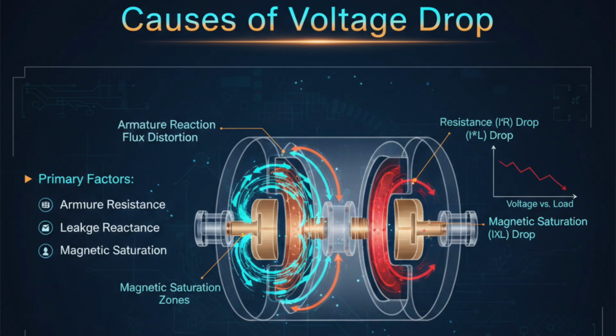Another major factor is armature reaction, the magnetic field created by stator currents that distorts or weakens the main rotor field. You can see this effect represented by bent and distorted flux lines in the graphic. Magnetic saturation of the core also limits how much additional flux can be produced even when excitation is increased. Together, these phenomena explain why voltage falls under load and why automatic voltage regulators must constantly adjust excitation current.